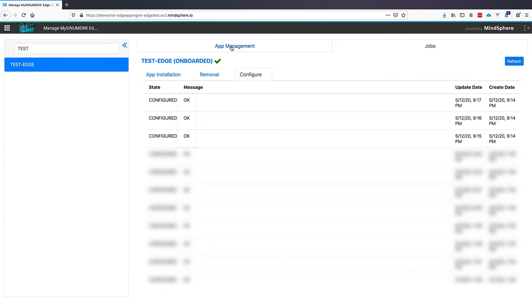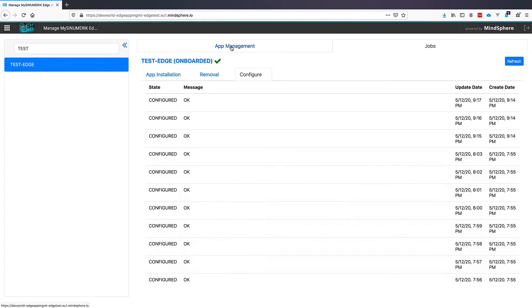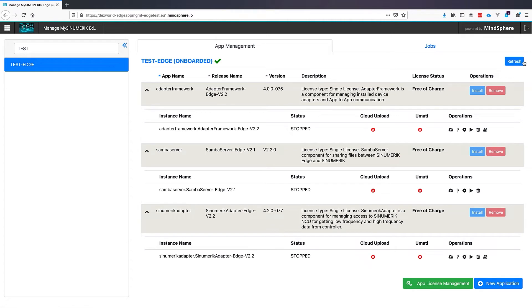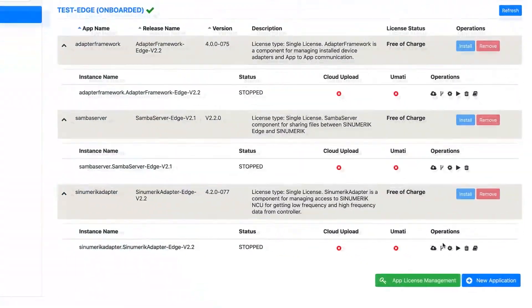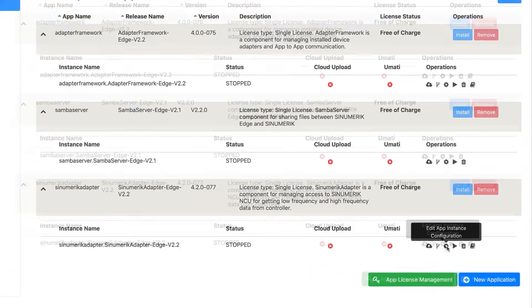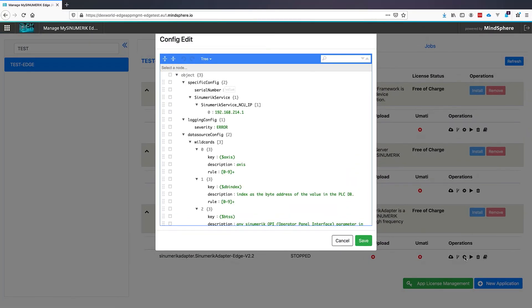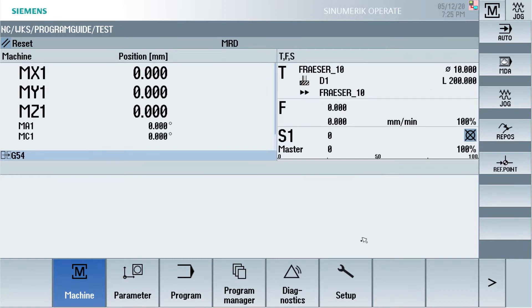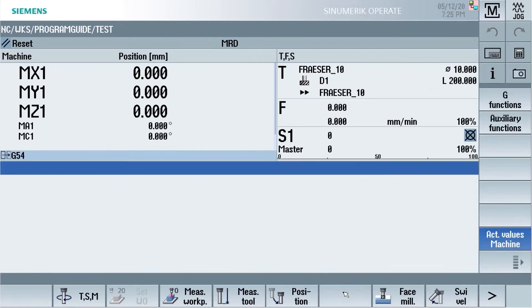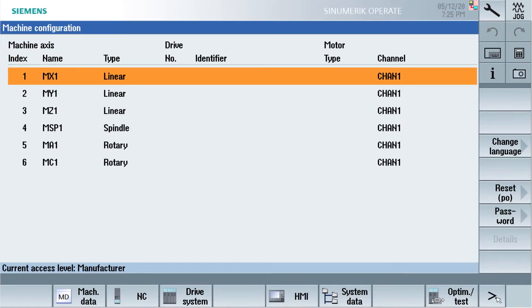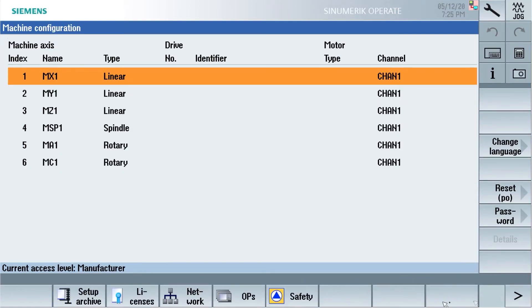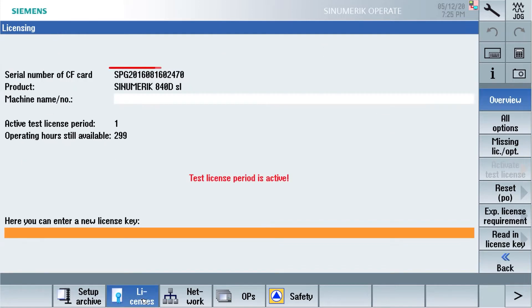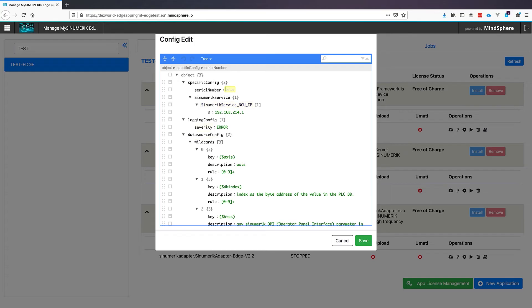If this is done, we need to configure some applications. We will start with the SINUMERIK Adapter. You see the small gear and the small gear is to configure an application. First we need the serial number of our SINUMERIK CF card. Therefore we change over to our SINUMERIK Controller and with menu Select, Setup and Licenses, we can see the serial number of our CF card. We can mark it down or copy it to use it in our configuration page. We will paste the serial number from our SINUMERIK into the configuration and click Save.